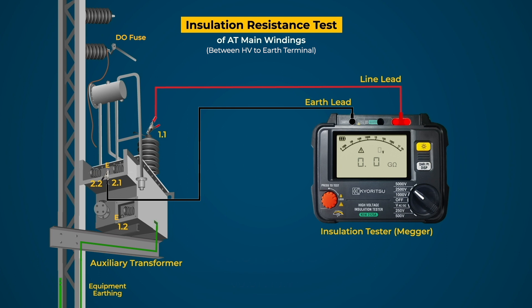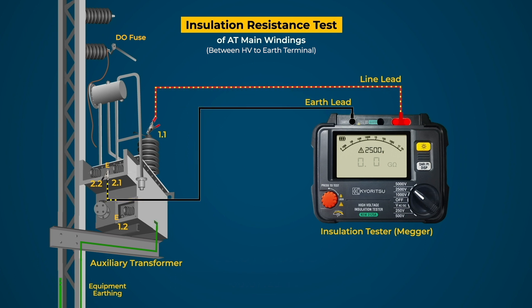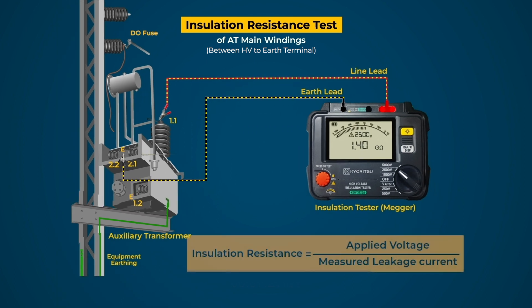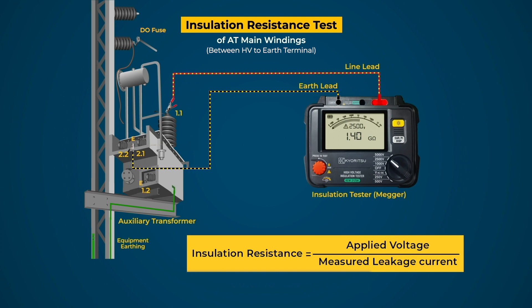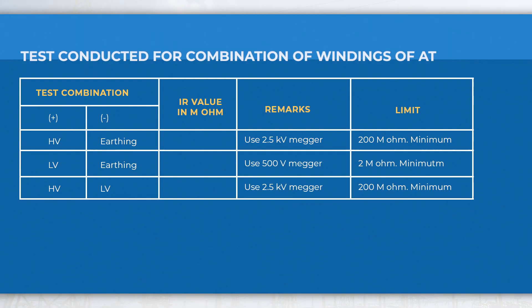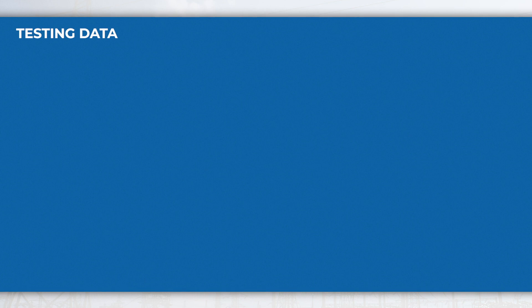On pressing the test button of the tester, 2.5 kV DC voltage is applied across HV and earthing. As a result, leakage current will flow in the circuit, and the tester will measure this leakage current and calculate the insulation resistance by the ratio of applied voltage and measured leakage current. The insulation resistance value may be noted from the display. The same test is to be conducted for the combination of windings as shown in the table. Testing data may be recorded in this format for further investigation and future reference.